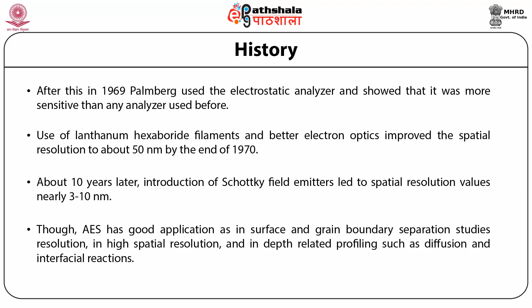Now, to start with, we need to know what is AES. AES, or Auger electron spectroscopy, is a surface analytical technique, and it was the first technique used for surface analysis of solid materials, followed by X-ray induced photoelectron spectroscopy. It uses the Auger electrons emitted from an electron beam interaction with the sample to determine elemental information about the surface of the sample. The Auger electrons are typically very low energy electrons, less than 2000 volts. These electrons can only escape from the top 50 angstrom of the sample.